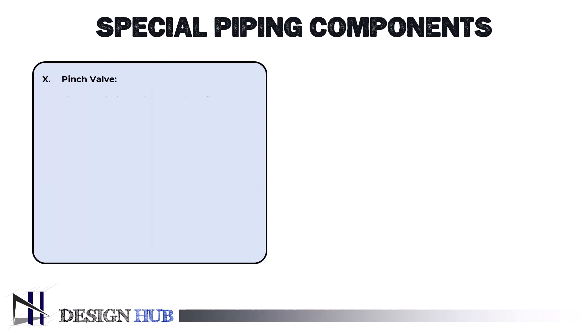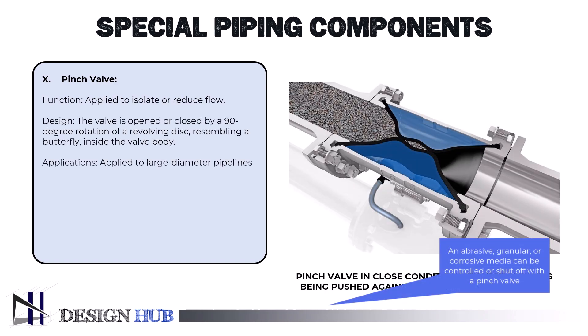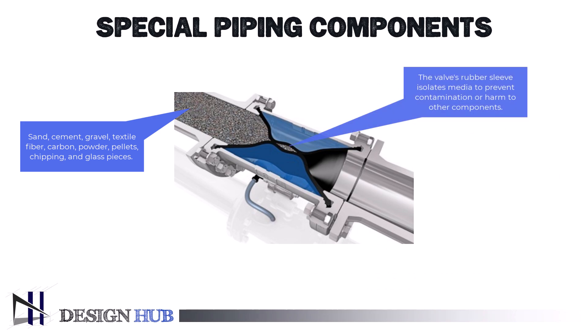Lastly, we will look at the pinch valve. An abrasive, granular, or corrosive media can be controlled or shut off with a pinch valve, which is a two-way valve. The valve can be opened or closed using pressured air. A broad variety of media can flow through the bore when the valve is in the open position, where it is unrestricted. To prevent contamination or harm to the valve's other components, the flexible internal rubber sleeve isolates the media from the rest of the valve. An air-operated pinch valve consists of an elasticized reinforced rubber hose, a housing, and two socket end caps, also known as flanges.